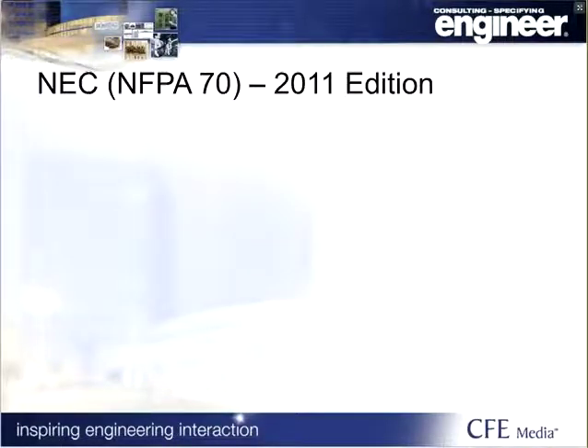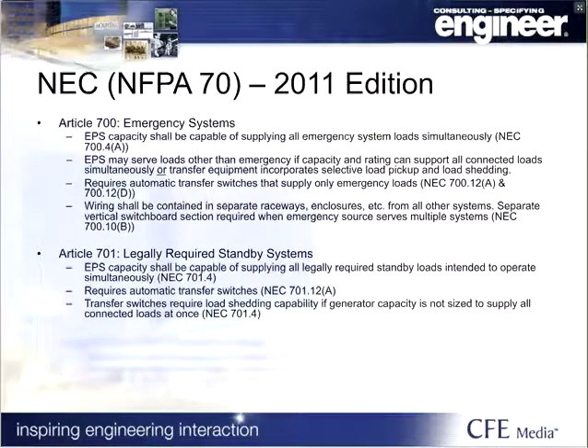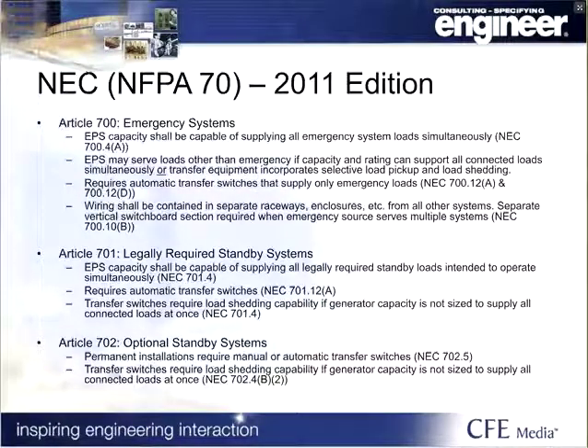Where Article 445 provides requirements for generators, Articles 700, 701, and 702 provide requirements for the use of generators. An EPS that serves an Article 700 emergency system is required to have the capacity to supply all connected loads simultaneously from the emergency system. The EPS is allowed to also serve non-emergency systems, but will require load pickup and shedding ability for the other systems, unless the EPS has the capacity to supply all connected loads from all systems. Article 701 legally required standby systems are required to have an EPS with the capacity to serve all loads intended to operate simultaneously. And since Article 702 optional standby systems are not code required, there are no EPS capacity requirements.